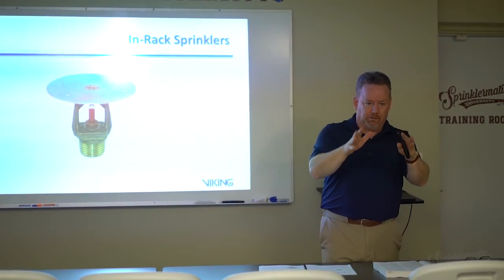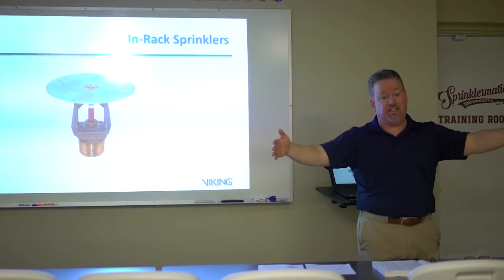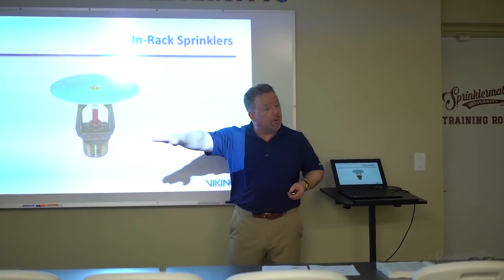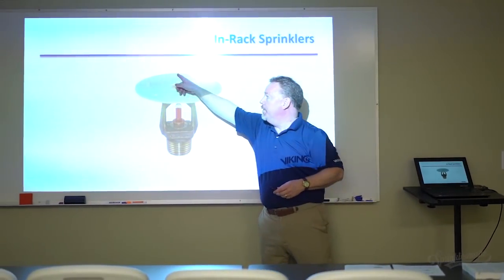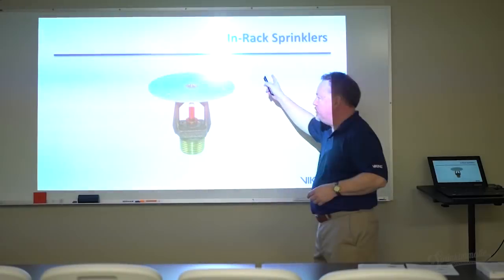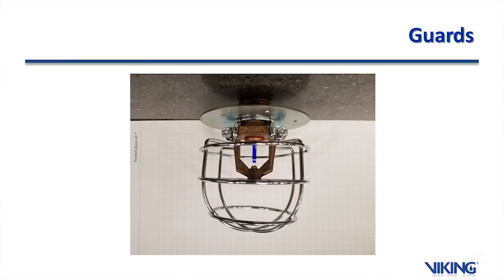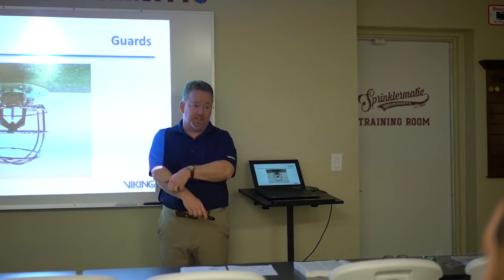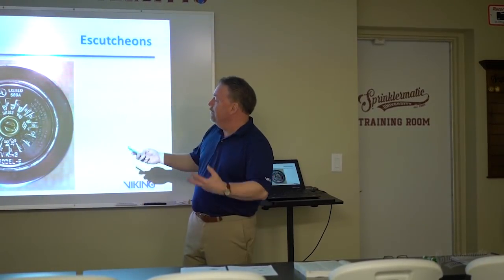In-rack sprinklers are designed for rack storage installations where sprinklers in the racks themselves are required to deliver protection directly to burning commodity within the rack — which can be stacked up to 45 feet or more, making ceiling-only sprinklers insufficient. The disc on an in-rack sprinkler isn't for heat collection; it protects the fusible link from being wetted by spray from sprinklers above, which would delay its operation. In areas where sprinklers could be damaged, a listed guard compatible with that specific sprinkler should be used.